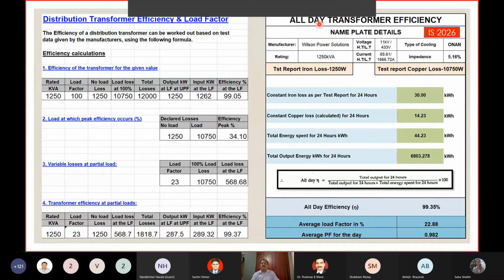So what we have done is we have used an all-day transformer efficiency calculation in an Excel. There are two types of Excels that we use. One uses the all-day energy and then arrives at the output kilowatt-hour and then works out the transformer efficiency all day. So as you can see here, the average load factor was 23%. The power factor for that day was 0.982 and the all-day efficiency of the transformer was 99.35%.